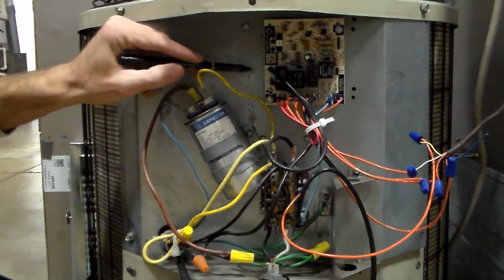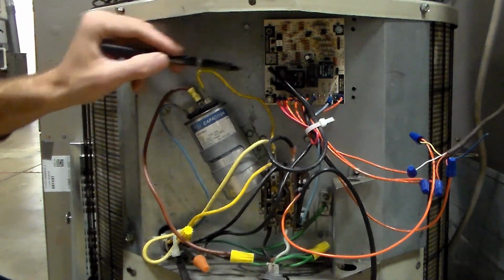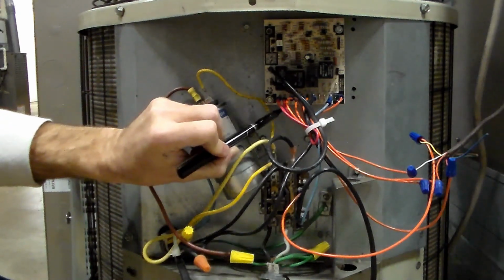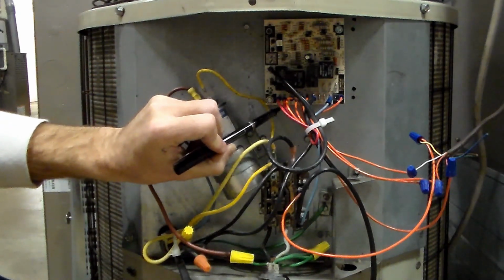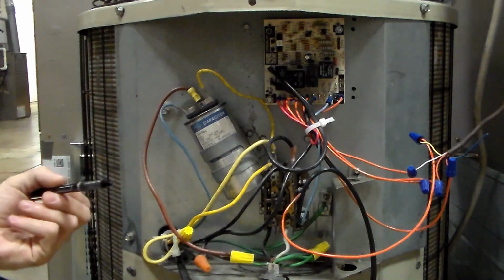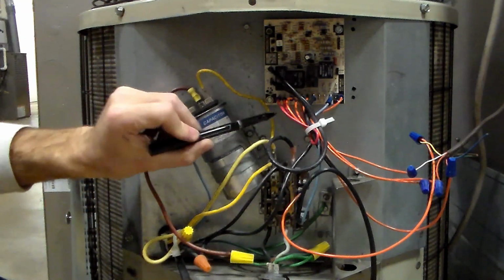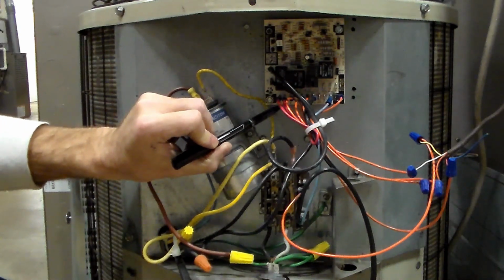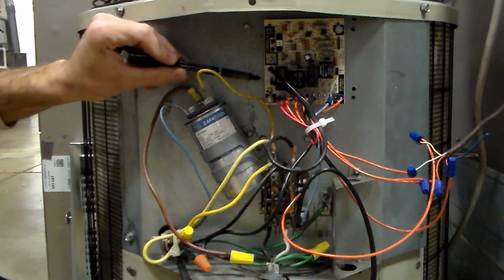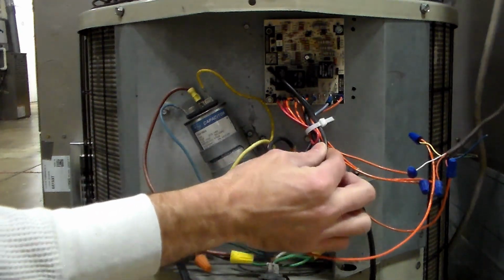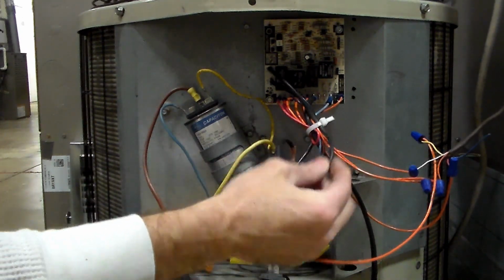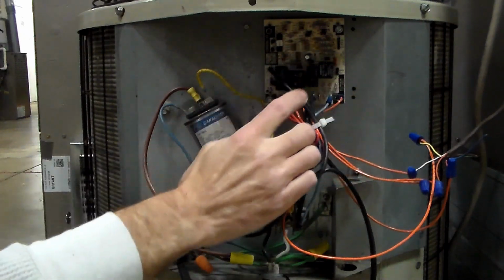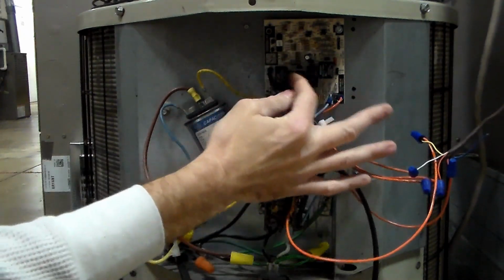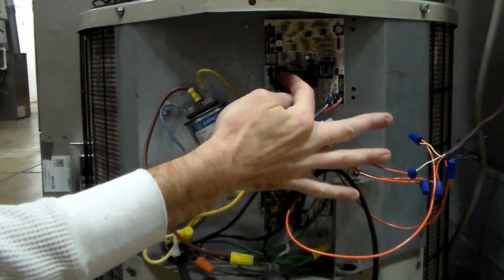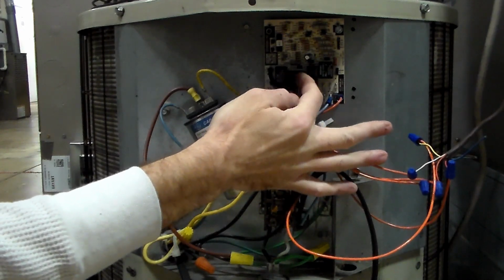So instead of being labeled fan, this one's labeled DF1, DF2, and then down here we've got this DFT. To keep it straight, the schematic should tell you if it's the original board. But the DFT, that's your sensor. With DF1 and DF2, we can clearly see one of them runs the high voltage, so that must be my fan relay. Plus, if you look close enough, you can see there's a black relay right there, and typically your fan wires are connected right next to a big black relay like that.